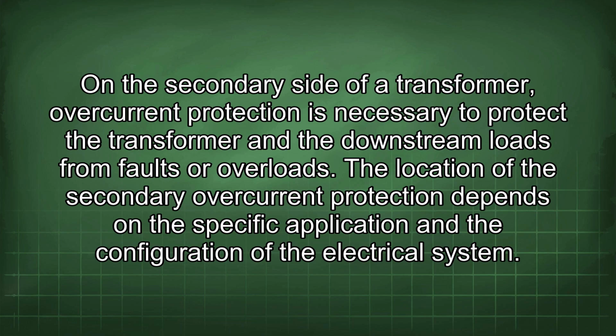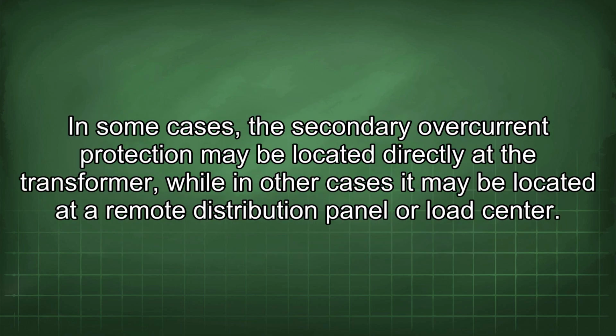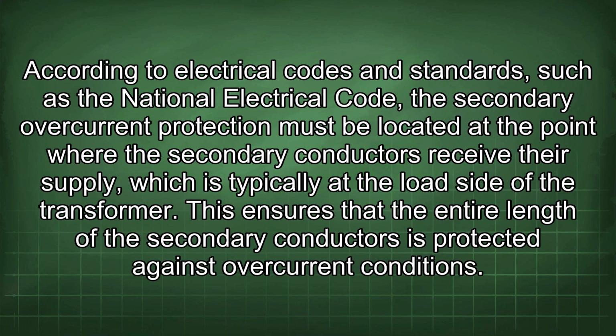On the secondary side of a transformer, overcurrent protection is necessary to protect the transformer and the downstream loads from faults or overloads. The location of the secondary overcurrent protection depends on the specific application and the configuration of the electrical system. In some cases, a secondary overcurrent protection may be located directly at the transformer, while in other cases it may be located at a remote distribution panel or load center. According to electrical codes and standards, such as the National Electrical Code, the secondary overcurrent protection must be located at the point where the secondary conductors receive their supply, which is typically at the load side of the transformer. This ensures that the entire length of the secondary conductors is protected against overcurrent conditions.